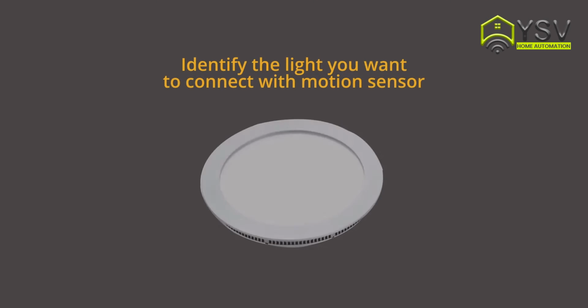Now identify the light you want to connect with the motion sensor. Also make sure you have a neutral wire inside the panel, as a neutral connection is mandatory for the motion sensor. In the absence of a neutral wire, please draw one from the nearest point, otherwise the installation cannot be completed.